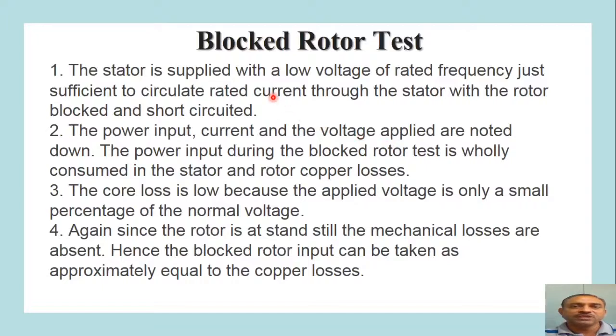Now the block rotor test. As the name itself suggests, during this test the rotor of the motor is blocked. With this condition we have to apply to the stator a very low voltage at the rated frequency. Block rotor means that the rotor itself is short circuited. This condition is similar to the short circuit test on a transformer. The power input, current and voltage applied during this test will be called WSC, ISC and VSC.